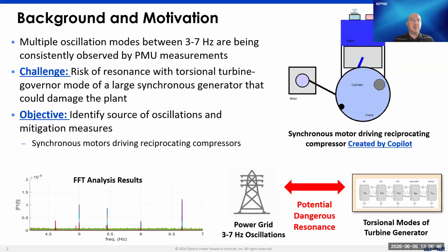So let me start with background and motivation. Entergy has been consistently observing small magnitude oscillations with a wide frequency range between 3 to 7 hertz in different regions across the Entergy grid territory. They have been observing these using PMU measurements for a while now. Initially, it was not a big concern.